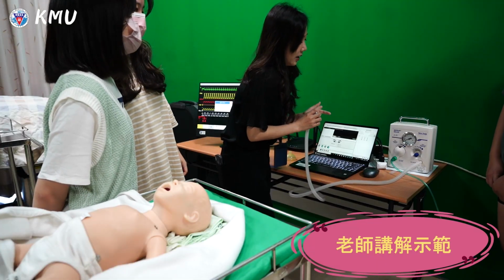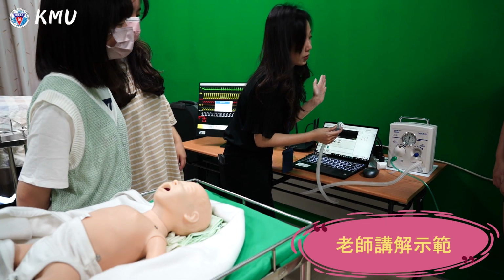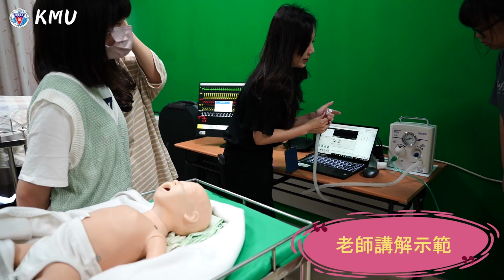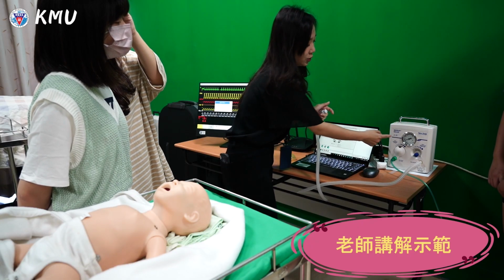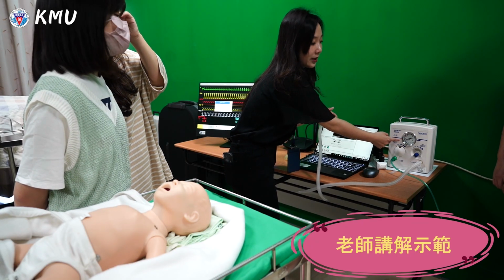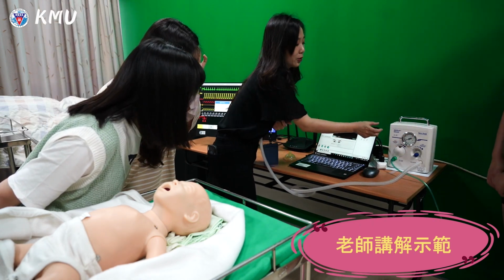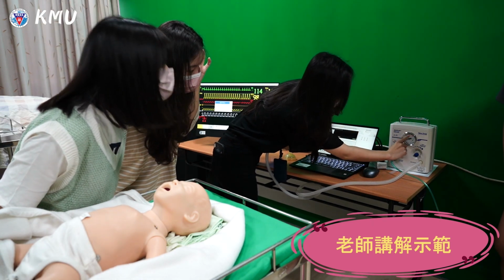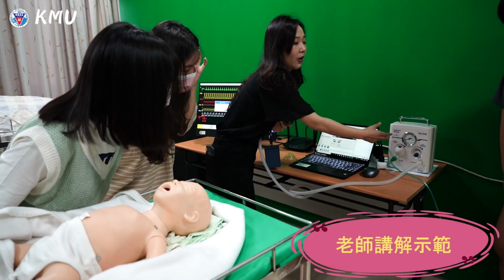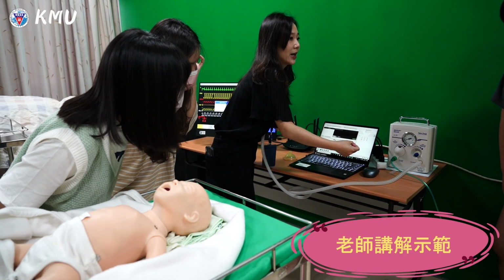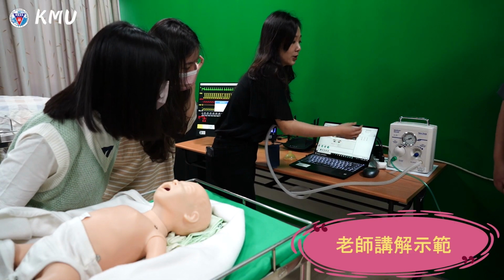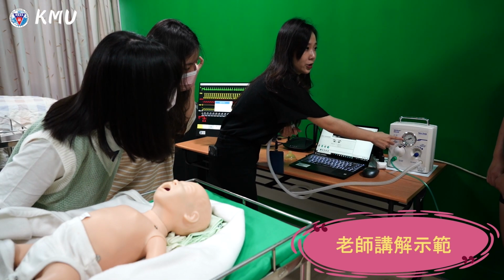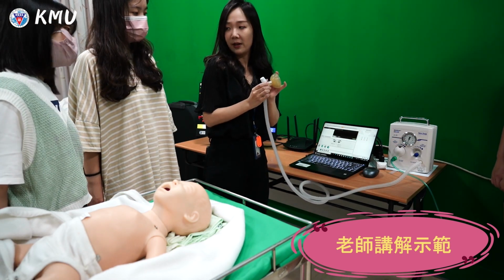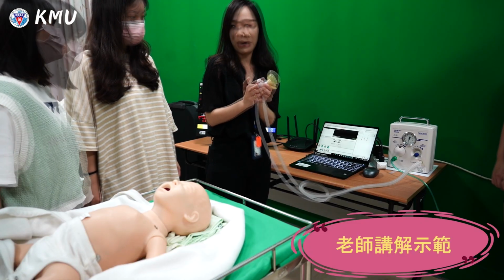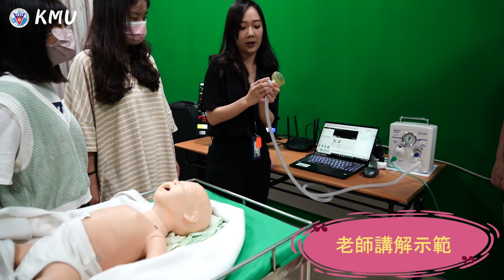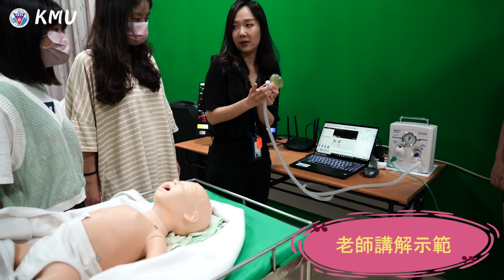Okay? So when you release, it will go back to 0. But when you cover it, it will be at the pressure of 20. The red one means it's over the highest pressure the baby can tolerate. Okay, so we have to be very careful about pressure. And then when the baby wants to expire the air, you release.